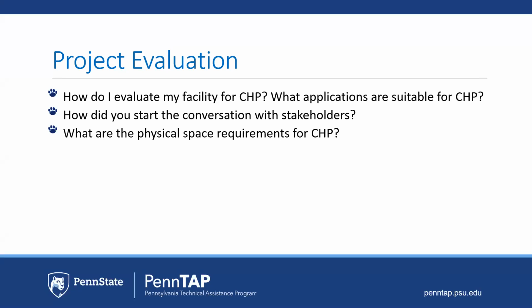We typically look at pad mounts that are vibration-isolated equipment, 8 to 20 feet, with 12 to 15 feet overhead, with a way to get exhaust out and cooling and fuel storage and fuel access. But it's highly site-specific—we've put them on top of hospitals and underneath facilities. It depends a lot on the sizes, whether you're getting multiple units, stacking them up, or have swing units. It's highly defined by the site-specific requirements.